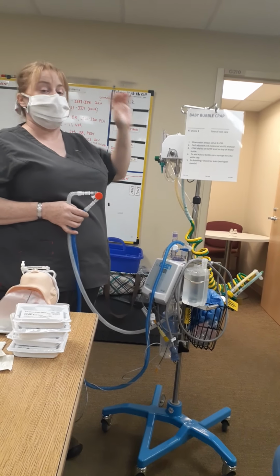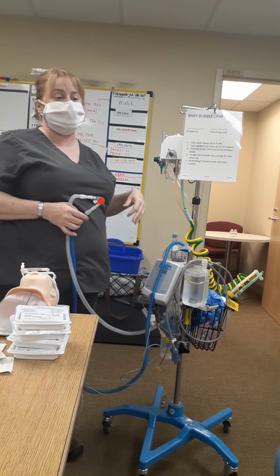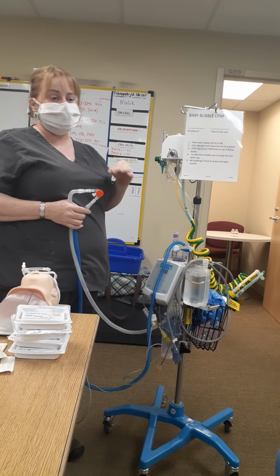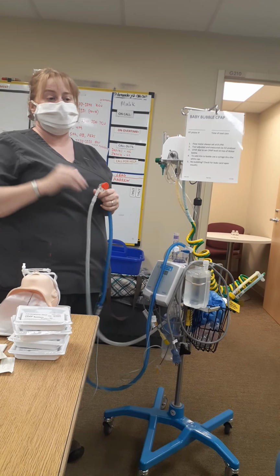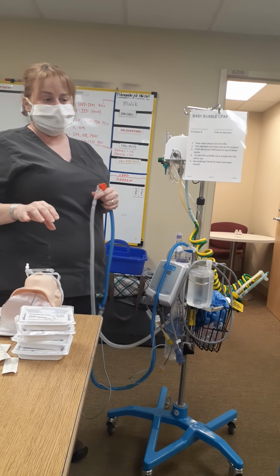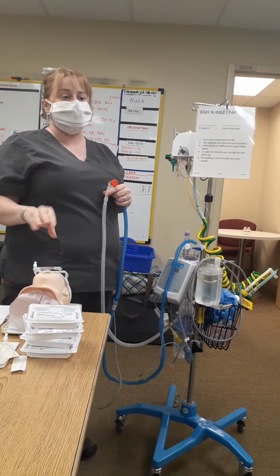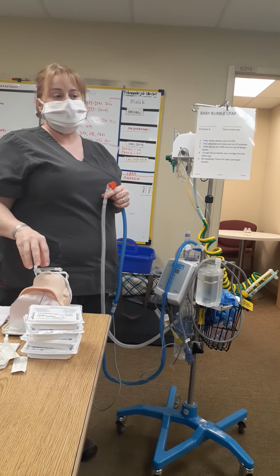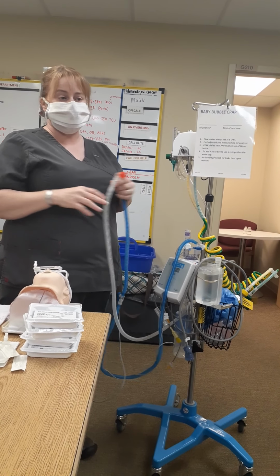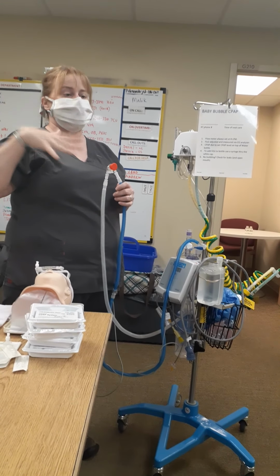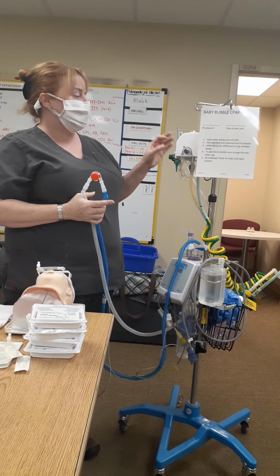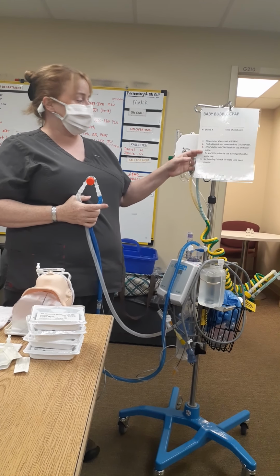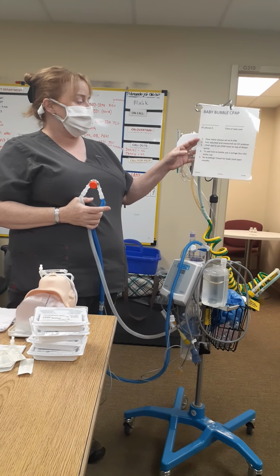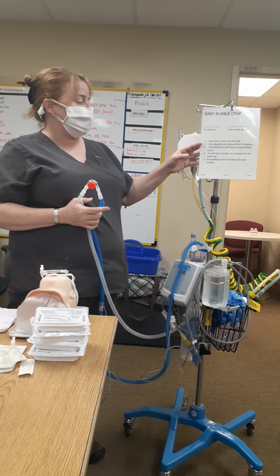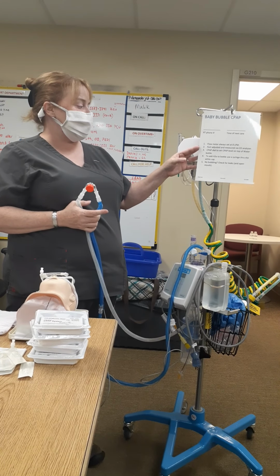So if they say, I need you to come at 3 o'clock to help me do care for the baby, they might want us just to come, and they might want to do skin check, so we might have to hold the T-piece mask on the baby while they do skin checks throughout, the head, take the bonnet off and everything. So this also has some cute little tips on it. Flow meter always set to 8. The FiO2 is adjusted and measured on the analyzer.